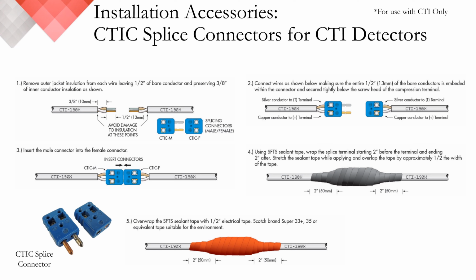When it comes to our CTI series, we must maintain and accommodate the dissimilar metals of copper and constantan when making splices. The CTIC splice connector is comprised of our dissimilar metals and provides the only acceptable means of repairing a fault within the CTI system. Aligning the appropriate conductors is crucial in maintaining the ability to accurately report temperature conditions when the detector is in a fault or alarm state.